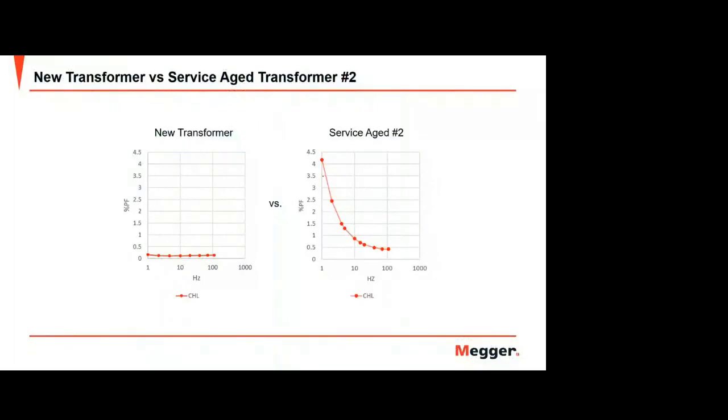And when you compare the narrowband DFR response, it's still good for transformer number 1. Now this is transformer number 2, still identical to transformer number 1. They have the same specification and the same year of manufacture. But what happened with this transformer number 2?